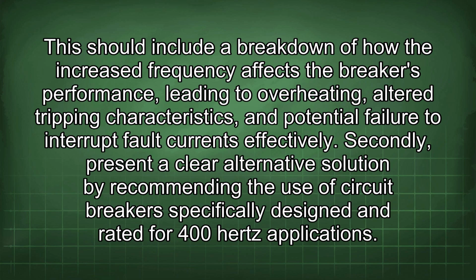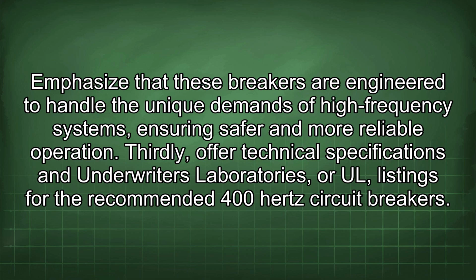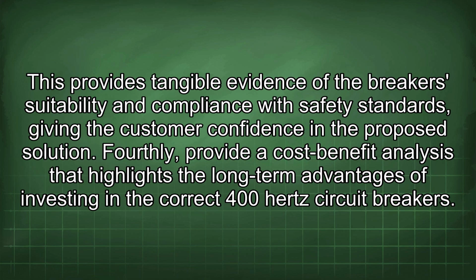Secondly, present a clear alternative solution by recommending the use of circuit breakers specifically designed and rated for 400 Hz applications. Emphasize that these breakers are engineered to handle the unique demands of high-frequency systems, ensuring safer and more reliable operation. Thirdly, offer technical specifications and Underwriters Laboratories, or UL, listings for the recommended 400 Hz circuit breakers.